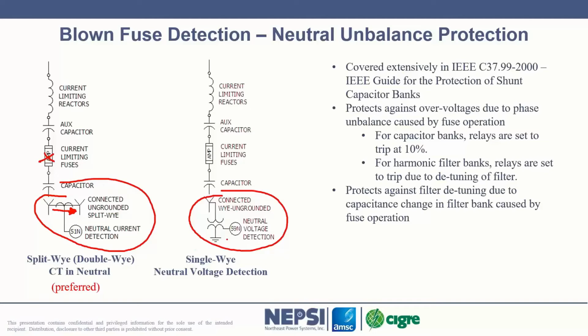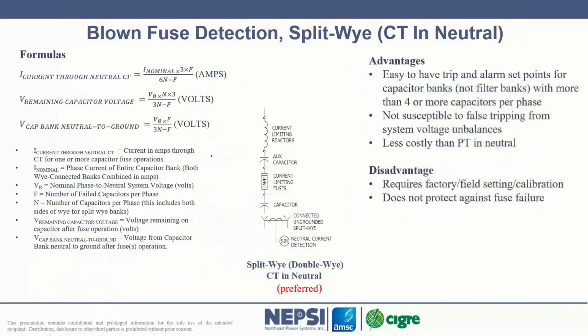And then again, we can use voltage for voltage. This is NEPSI's preferred reason. We can't get into reasons why, but there are reasons why the split Y with a CT in the neutral is a better choice for blown fuse detection. Incidentally, for externally fused capacitors, we also use a micro switch assembly here, and we detect a fuse operation here with the operation of a micro switch inside or connected to that fuse.